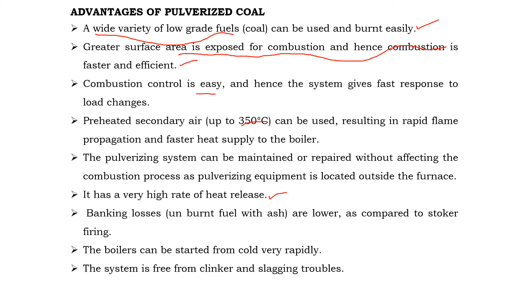Next advantage is that it has a very high rate of heat release. Banking losses are lower as compared to stoker firing. The boilers can be started from cold very rapidly. And the last advantage is the system is free from clinker and slagging troubles.